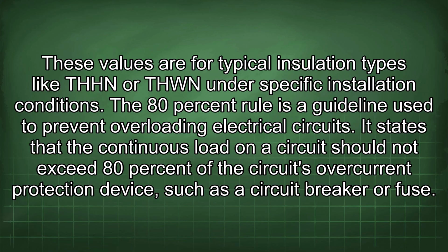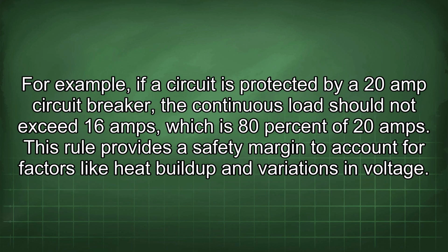The 80% rule is a guideline used to prevent overloading electrical circuits. It states that the continuous load on a circuit should not exceed 80% of the circuit's overcurrent protection device, such as a circuit breaker or fuse. For example, if a circuit is protected by a 20 amp circuit breaker, the continuous load should not exceed 16 amps, which is 80% of 20 amps. This rule provides a safety margin to account for factors like heat buildup and variations in voltage.